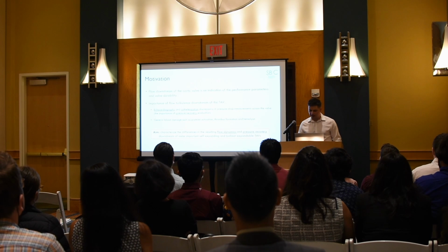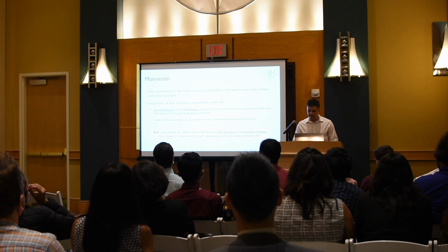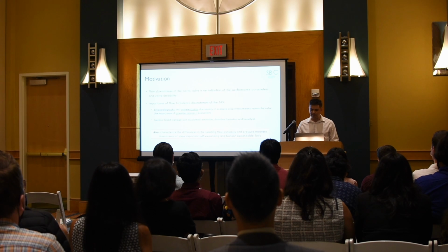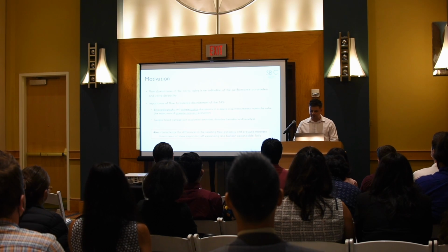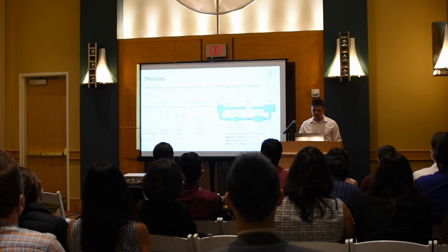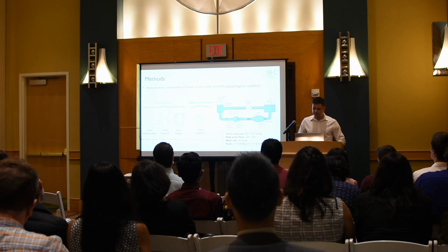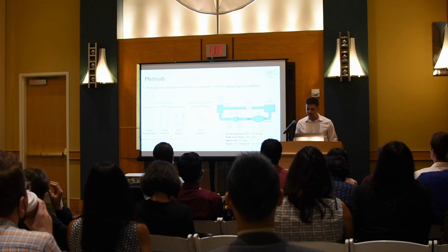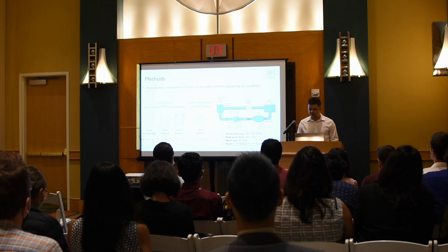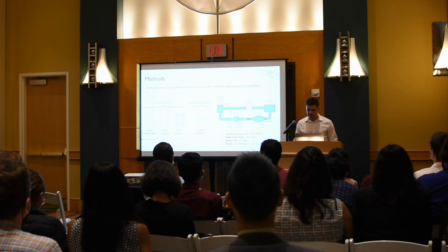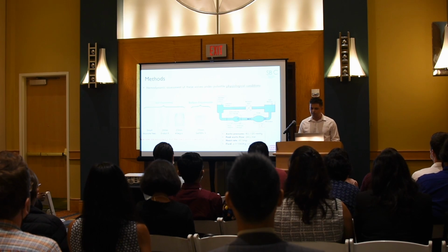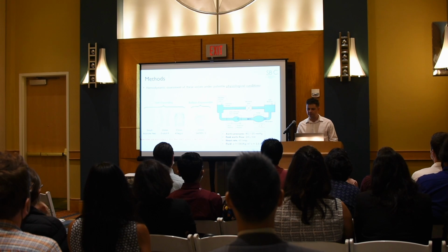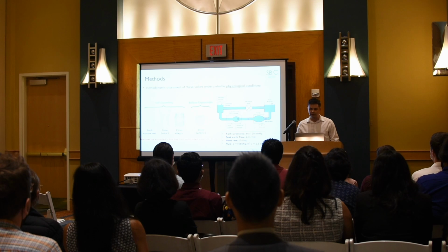So in this study, we aim to characterize the difference in the flow dynamics and pressure recovery downstream of multiple self-expanding and balloon-expandable transcatheter aortic valves. In this study, the hemodynamic assessment of the 26 mm Evolut and the 23 mm Allegra as self-expanding valves, and the 23 mm SAPIEN 3 as a balloon-expandable valve, was performed in a left heart simulator under pulsatile physiological conditions. These valve sizes are accepted sizes to treat 20 to 23 mm annuli.